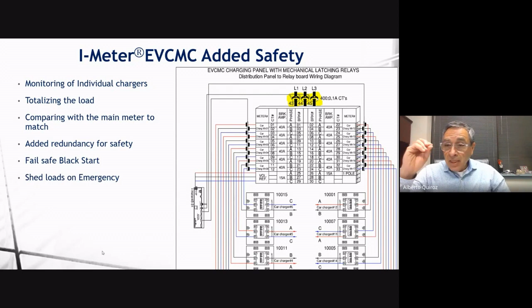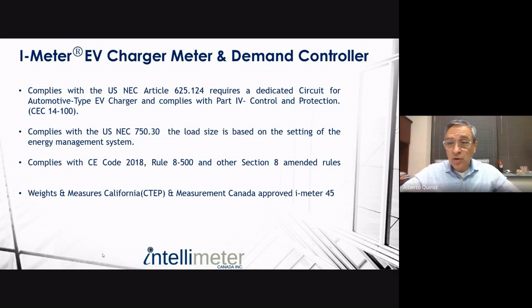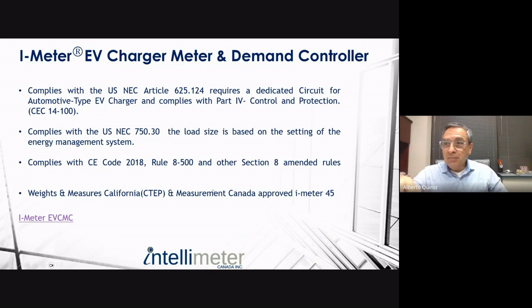It's allowed by the code, both in the United States and in Canada. The code allows sizing the feeder, the panel, and the breakers based not on the total aggregated load that's going to be installed, but on the capacity limited by the EVCMC. And of course, it's approved by Measurement Canada, so you don't have to worry about that part.